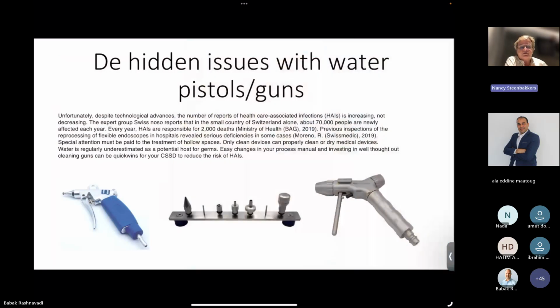Then also some people are using pistols or guns to flush all the channels, and there are also hidden issues with those guns. On the left side, you see the aluminum pistol. You can never clean it, and if you open it and take some samples, the growth of bacteria in that pistol is unbelievably high. You have to understand, if your endoscope is clean and disinfected and you want to dry the channels with the air pistol, and your air pistol never has any cleaning or disinfection, your air pistol will contaminate your endoscope again.